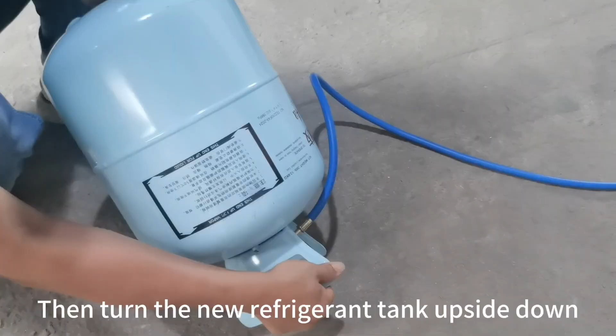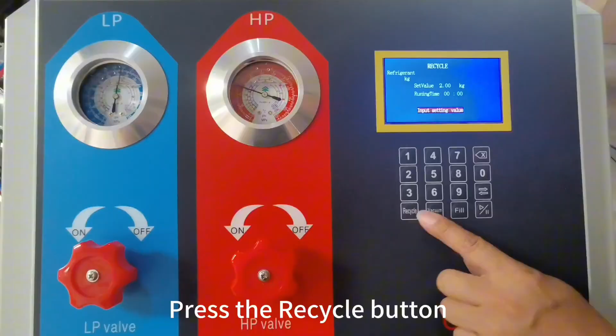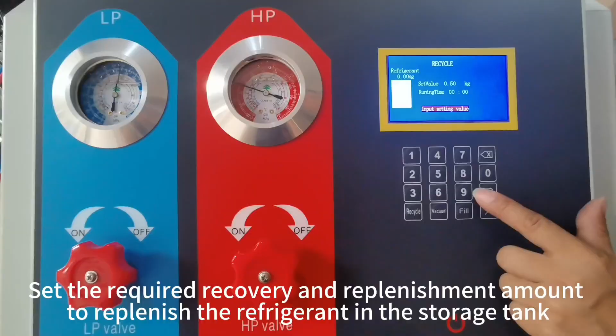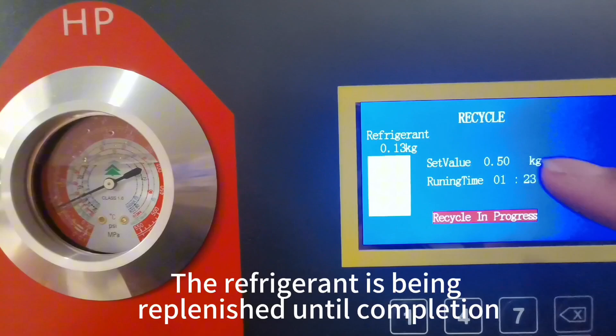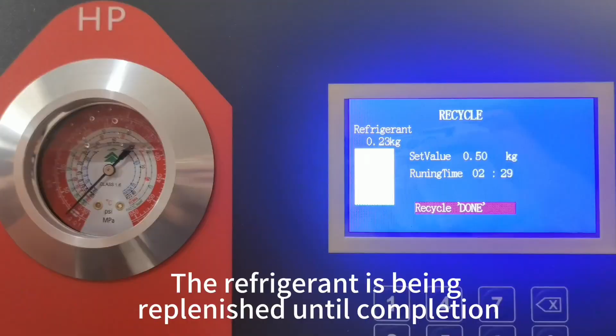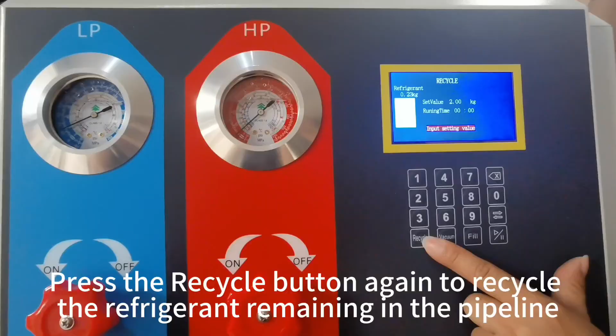Then turn the new refrigerant tank upside down. Press the recycle button. Set the required recovery and replenishment amount to replenish the refrigerant in the storage tank. The refrigerant is being replenished until completion. Stand up the new refrigerant tank and close the valve of the new refrigerant tank. Press the recycle button again to recycle the refrigerant remaining in the pipeline.